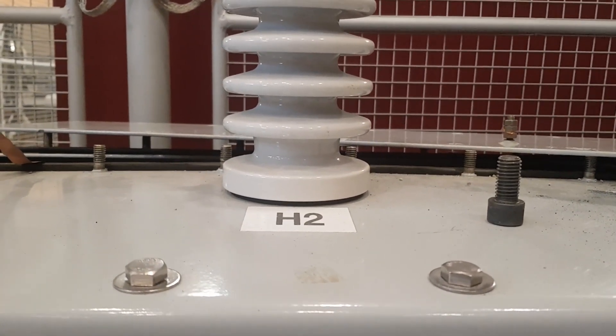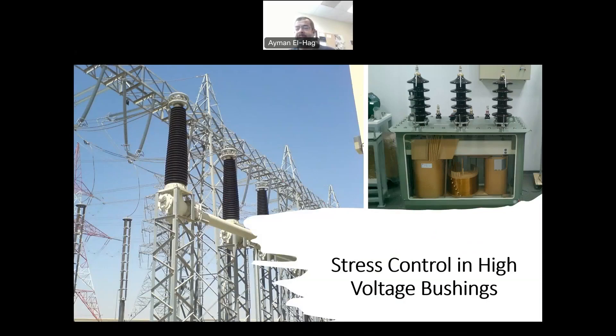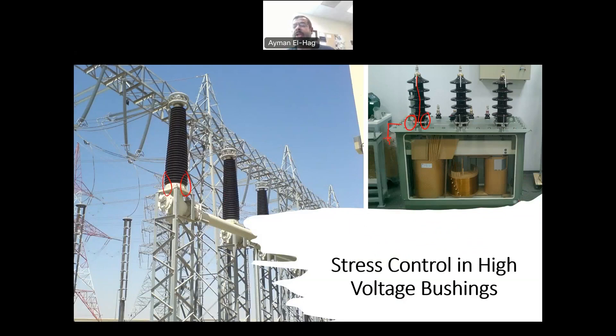The question is: how can we control the electrical stress in bushings? In this video we'll discuss this important issue about controlling electric field in outdoor high voltage bushings. So let's answer the question — how can I grade the electrical stress in transformers or circuit breakers where the high voltage conductor goes through the bushing and the tank is grounded? This susceptible area for high electrical stress may lead to corona initiation on the insulator surface, which might also lead to flashover.